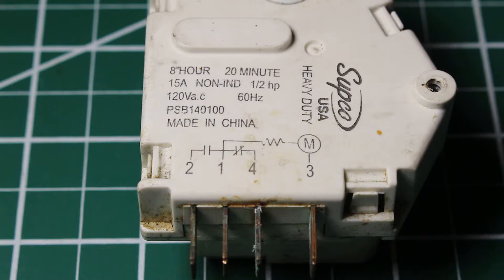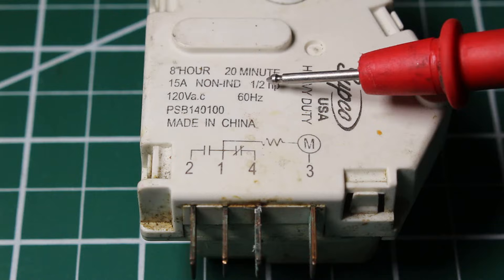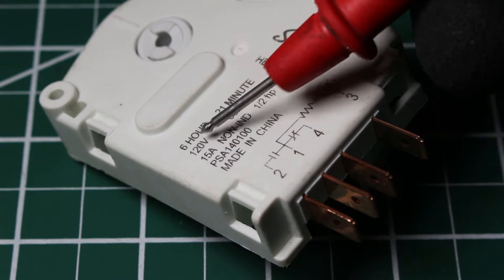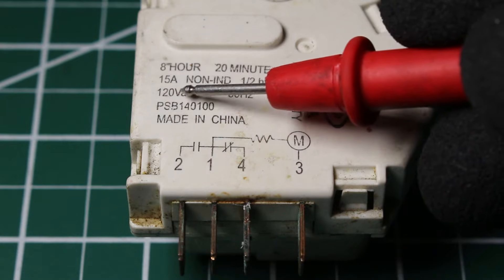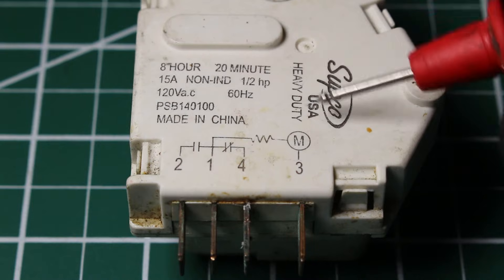Let's begin by going over the control. Attention to detail will take you very far, so let's see what we can actually read. This one says 8-hour runtime and 20-minute defrost. You might find other timers with different settings — this other control here is for 6 hours of runtime and a 21-minute defrost. It's rated for 15 amps, 120 volts AC, runs at 60 hertz, and is made by Supco — a heavy duty control.